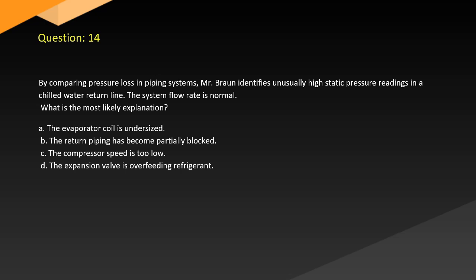Question 14. By comparing pressure loss in piping systems, Mr. Braun identifies unusually high static pressure readings in a chilled water return line. The system flow rate is normal. What is the most likely explanation?